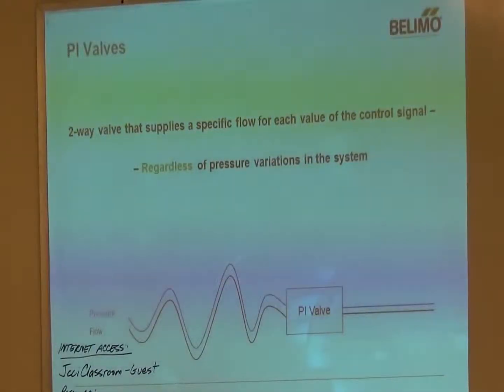Now in comparison to a pressure dependent valve, if you have that valve at 6 volts, you're not always going to get that same flow rate because, for example, say you've got a loop with 10 valves in it. Say 8 of those valves close off and you get a spike in your pressure on the last 2, you're going to get a spike in flow with that spike in pressure until you get a temperature change in the room that the building automation system will notice, and then it will back off on that valve. And then you're not going to be at 6 volts anymore. Your automation system is going to say, oh, we don't need as much flow anymore, so bring it back to 4 volts, 3 volts, whatever the case may be.